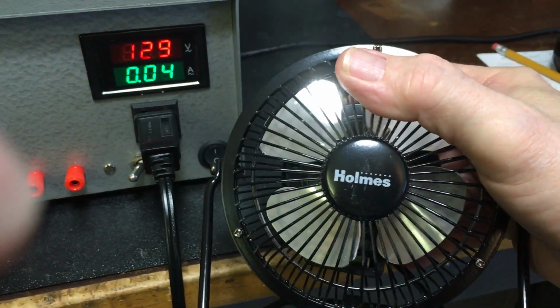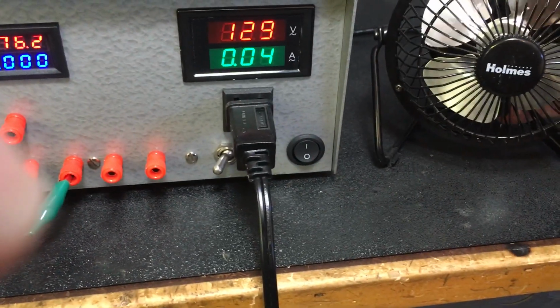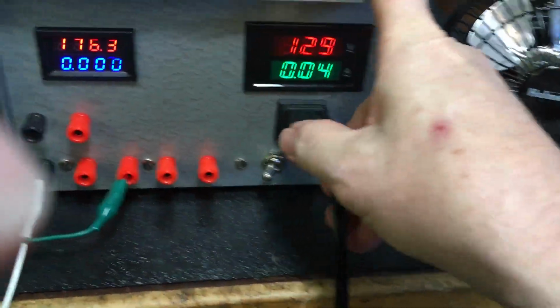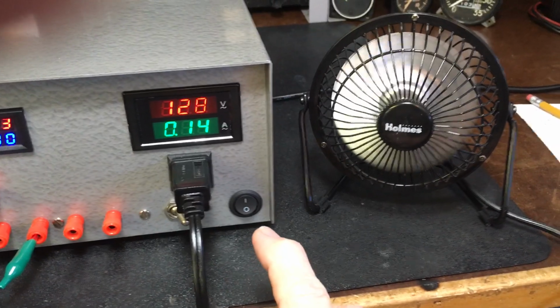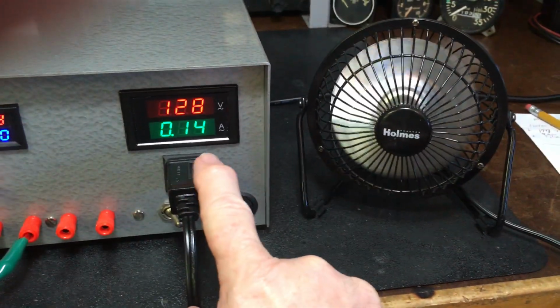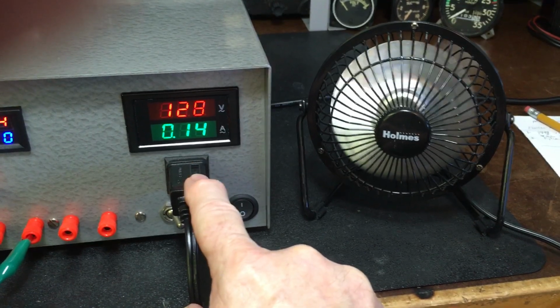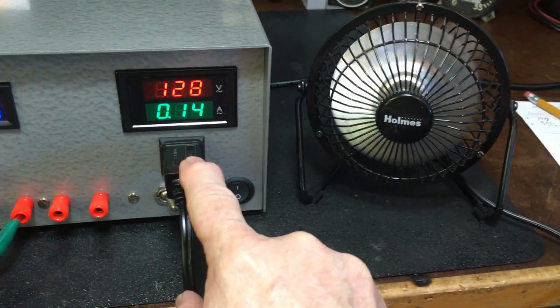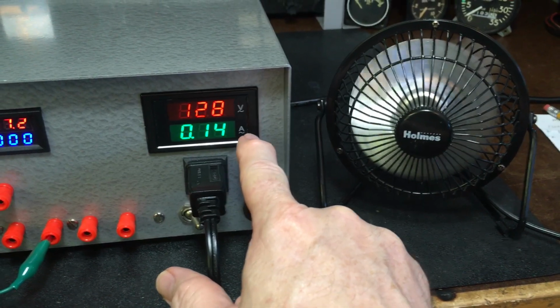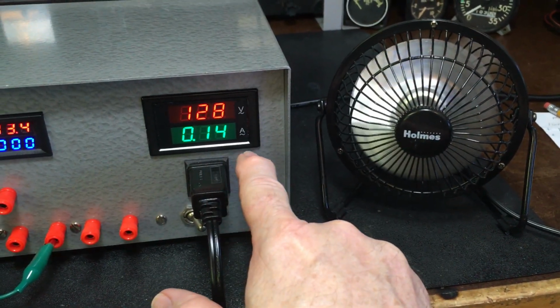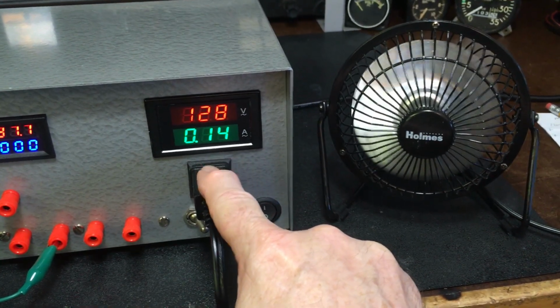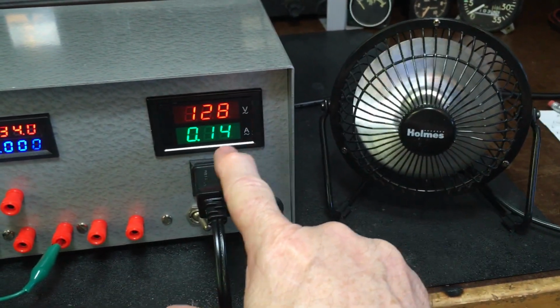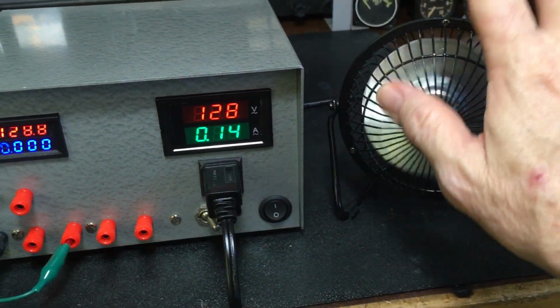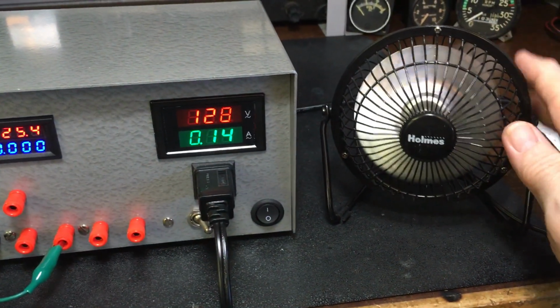Let's give a little demonstration. This is a 35 watt cooling fan, let's see if it indicates 35 watts. We got it plugged in here - oh, that's nice and cool on a hot day. We're reading 0.14, but remember we subtract 0.04 amps for the meter itself, so it's really 0.10 amps. If we multiply 0.1 times 128 volts, we get 12.8 watts, which is pretty close to the label on this fan that says 13 watts.